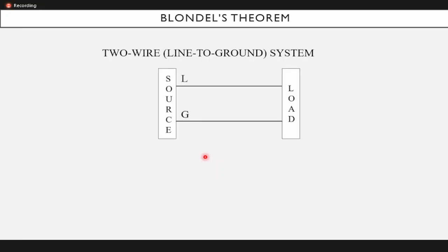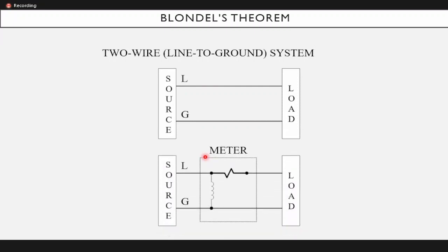Shown here is the diagram of a single phase, two wire, line to ground system. This is typical for a single phase residential connection if the source is line to ground connected. The potential coil is connected across the line and the ground, and the current coil is connected in series with the line. The current coil measures 100% of the current flowing through the line.